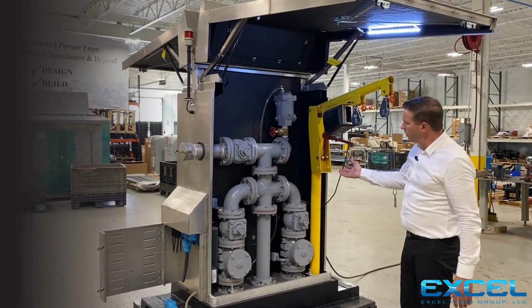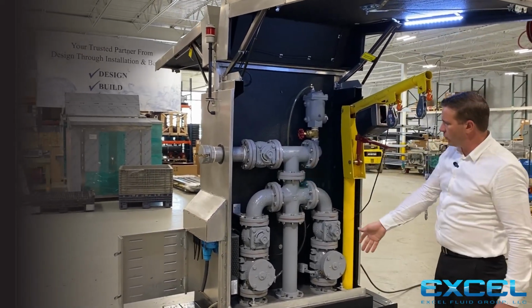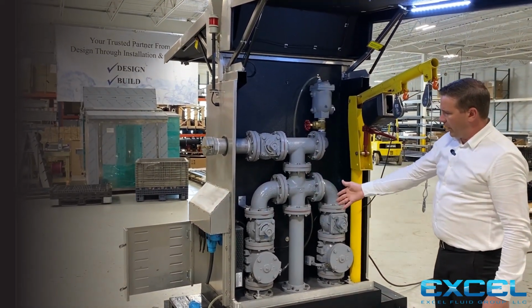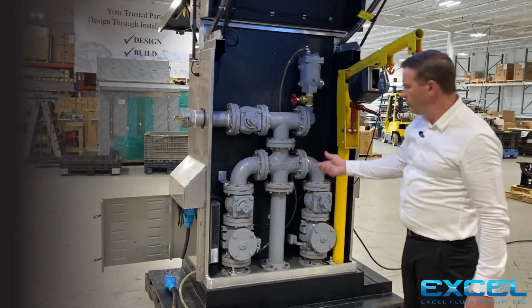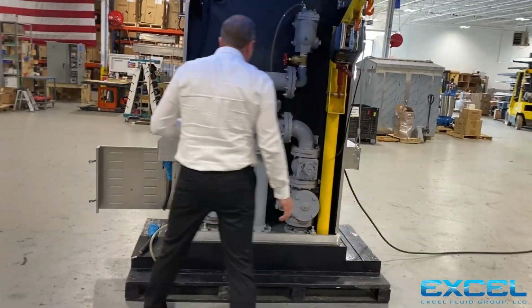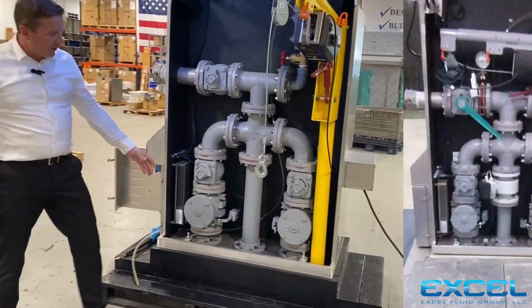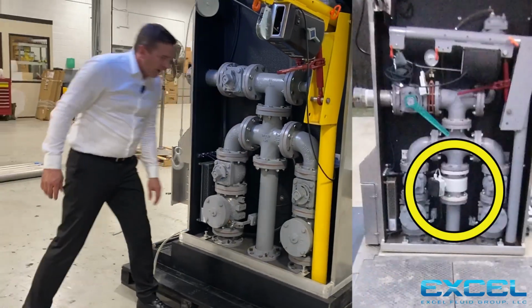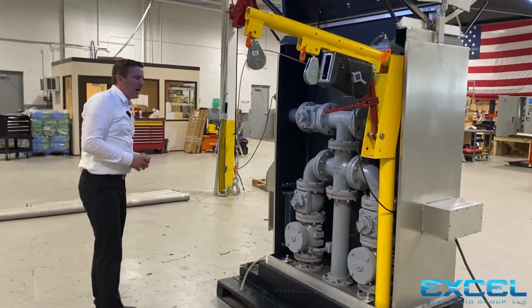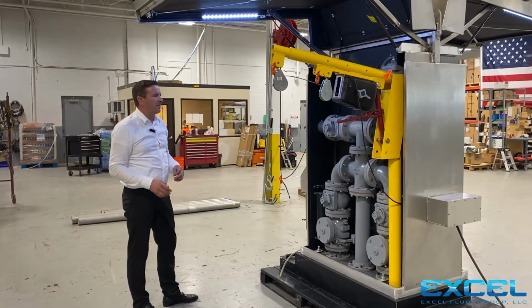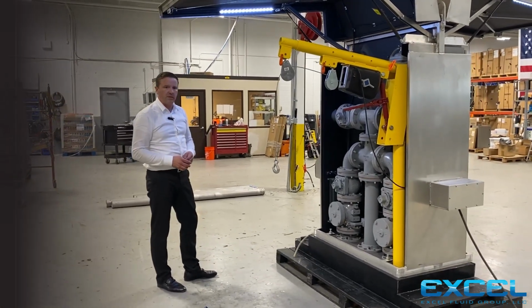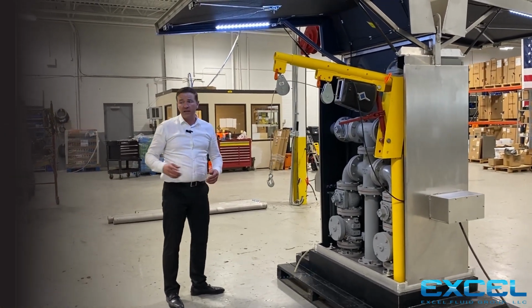Ductile iron piping shown here, air release, which drains to the wet well. We have our heater, which is thermostatic controlled and is able to communicate with your control scheme. If we had a flow meter, it would go in here, and this can be made out of ductile iron as you see, different diameters. It could be PVC or CPVC, HDPE, or even stainless steel.